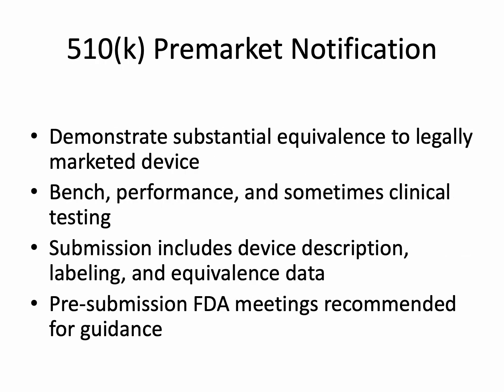The 510(k) pathway enables devices to demonstrate substantial equivalence to a legally marketed predicate device. This involves comparing technological characteristics, intended use, and performance data. Bench testing, functional performance testing, and occasionally clinical data are used to support equivalence claims. A complete submission includes device description, intended use statement, labeling, risk analysis, and supporting testing data. Early pre-submission meetings with FDA provide feedback on study design, data expectations, and potential gaps, reducing additional information requests and expediting clearance. A carefully planned 510(k) strategy aligns development with regulatory expectations, minimizes delays, and ensures compliance, facilitating safe, timely access to market.